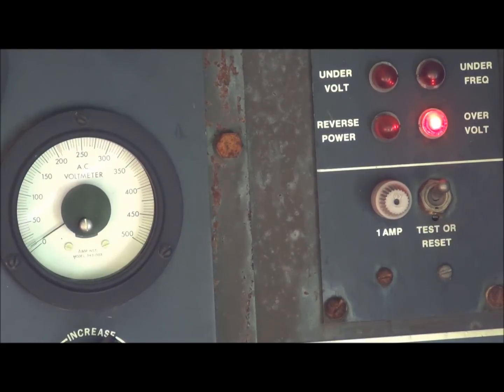As you can see right there, the generator started right up with no problem and came up to almost 260 volts that time. And as soon as I released the start switch, the over voltage light came on and the generator shut itself back down. So the safety is actually working the way it should. I think we just need to make some adjustments on the set point.